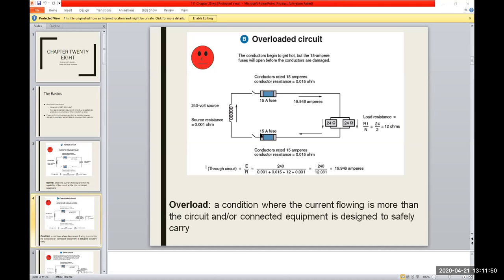If you take a cutaway of what it looks like inside, it's a little coil. So it would take a little bit of time, and then it reaches that overcurrent, and then it would trip, or it would blow the fuse. In some cases, a fuse just has a filament inside of it, and the filament basically will just burn away. Some are more solid core. It depends on the rating of the fuse. But when you get an overload, that's a condition where the current flowing is more than the circuit or the equipment is designed to safely handle. The reason they put it in there is fire protection. So if you're driving a motor or something like that, you'd much rather blow the fuse, which is cheap, than blow the motor, which can be pricey.